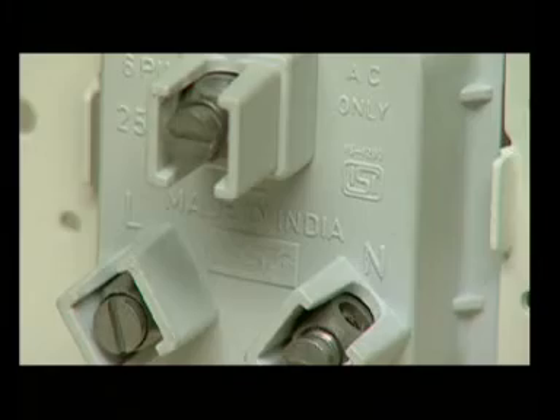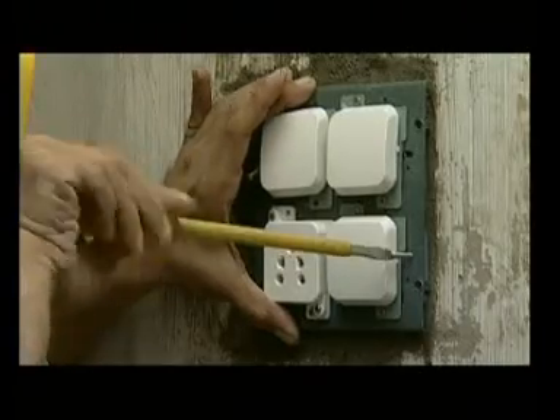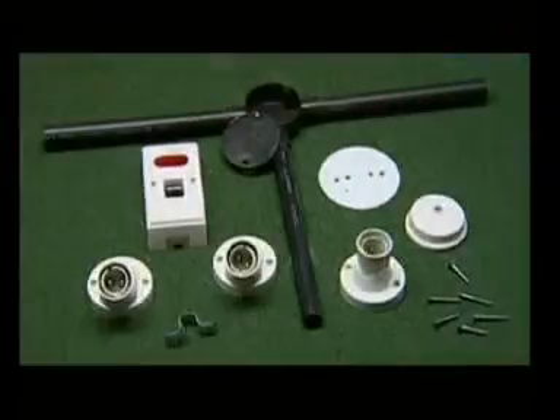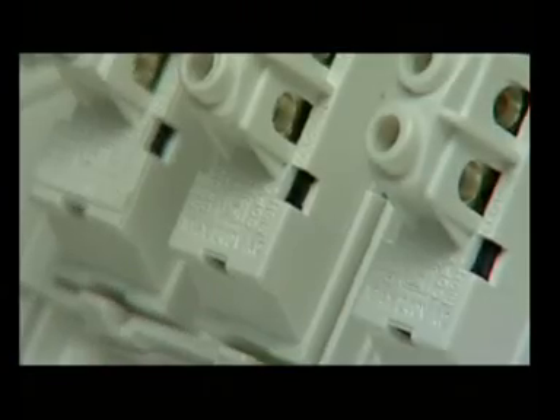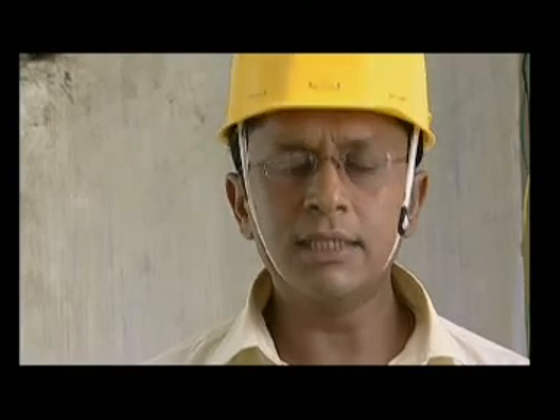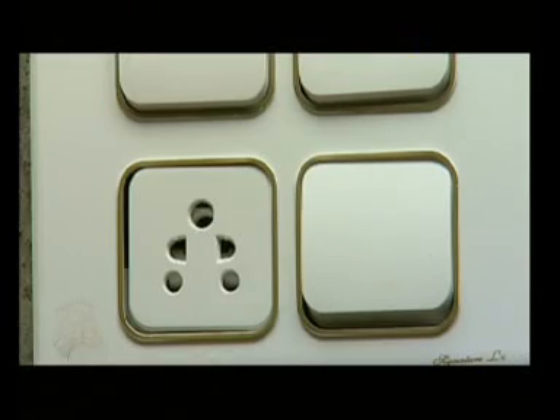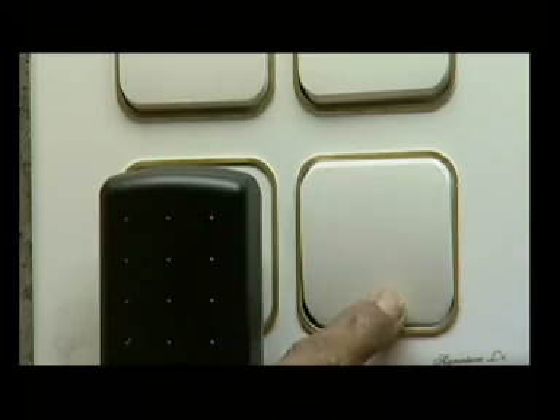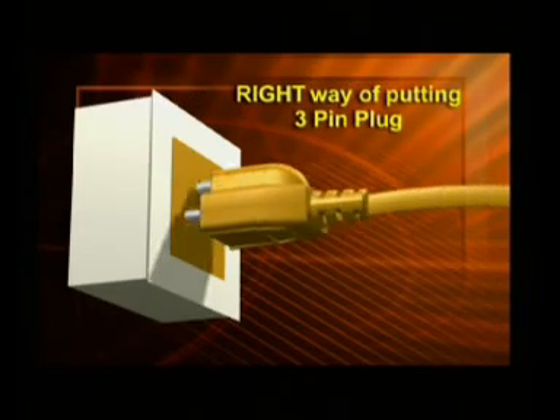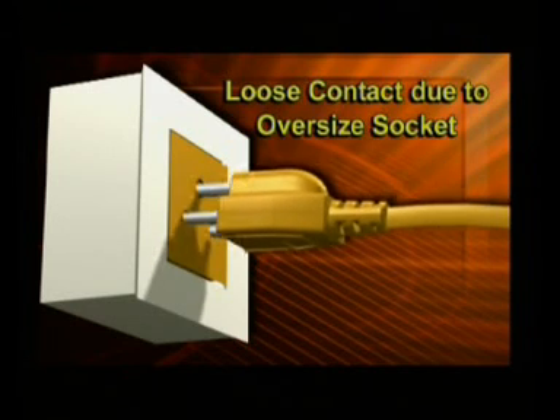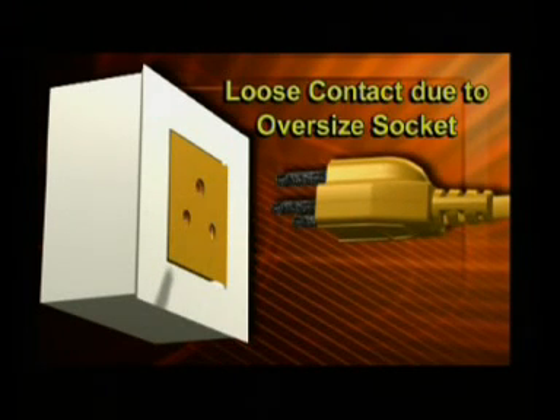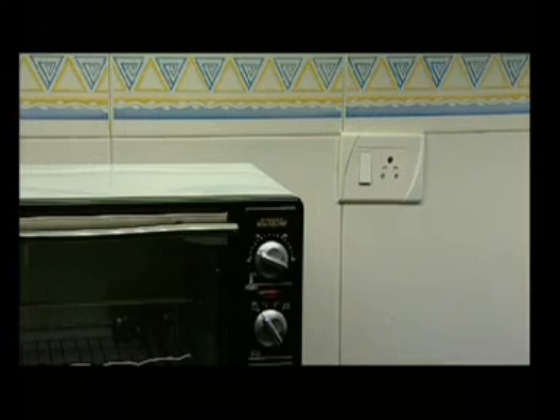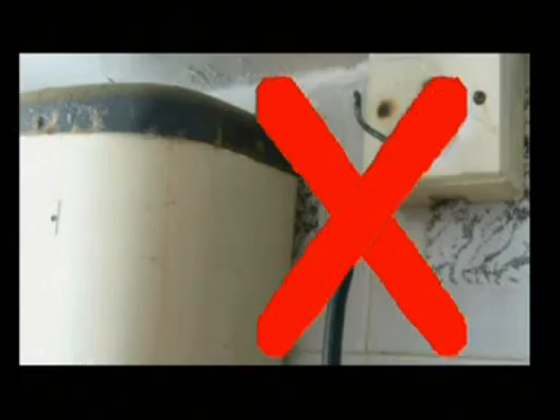Due to incorrect joints and loose joints and terminations, the temperature may rise and consequently a fire may occur. Hence, ensure that all joints and screws are properly tightened. All the switches, terminations, lamp holders, plugs and sockets must have an ISI mark. Always remember, all the switches must be in phase and use only shutter sockets. Do not use extra force to push the plug into the socket. And the most important thing, if the plug pins are not properly inserted into the socket, there is a danger of sparking and this may cause holes at that point. Always install a good number of 3-pin sockets. Do not use 2-pin sockets for equipment for which earthing is necessary.